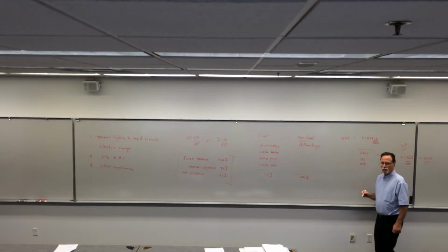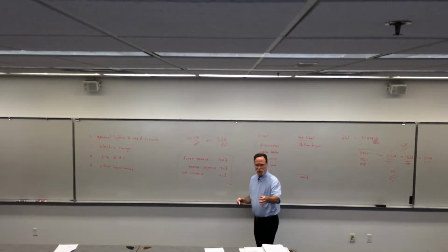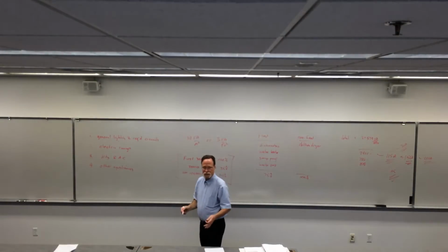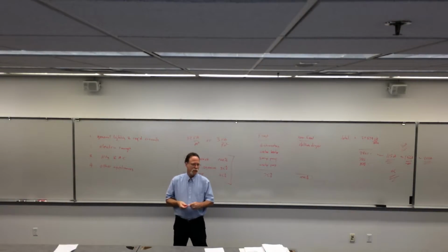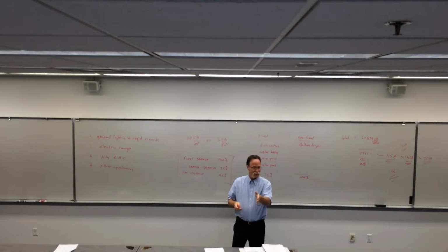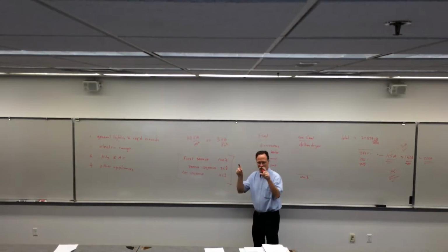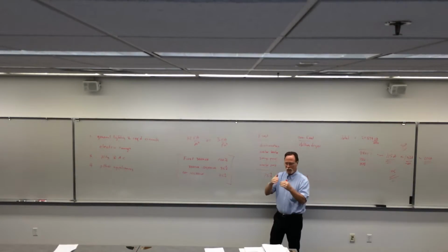Is that the size of the box? What does that mean? It is related physically, absolutely, the physical size, and why would that be? To put more things in there? Physically, to put more things in, absolutely, but as you have the bigger amount of power going through there, the spacing has to grow because you want a distance so arcing doesn't happen.